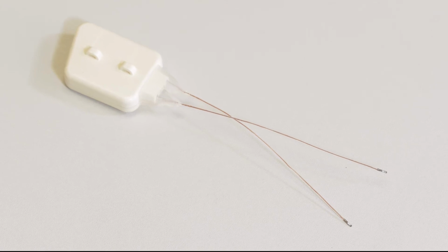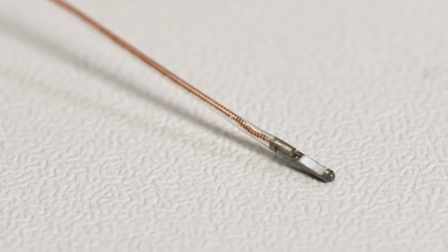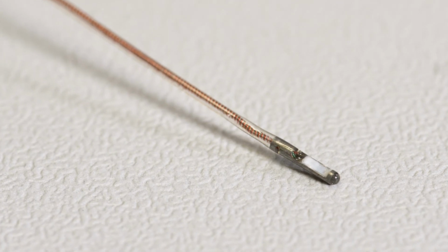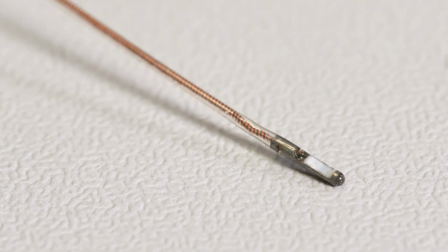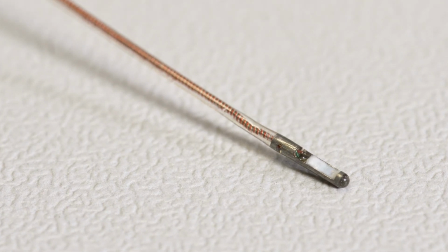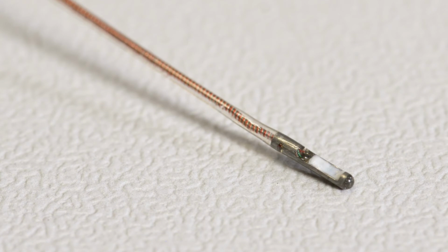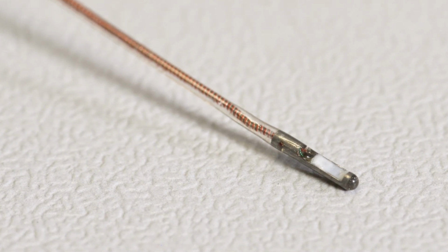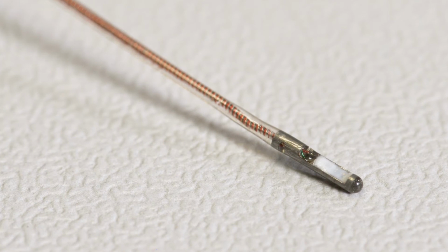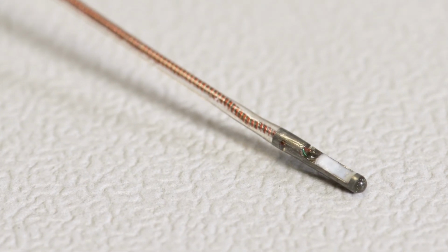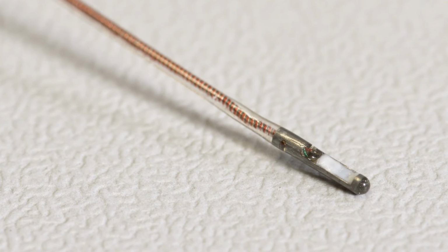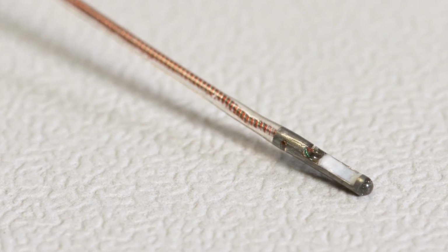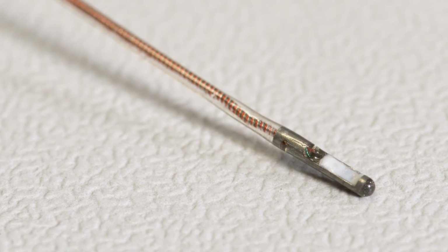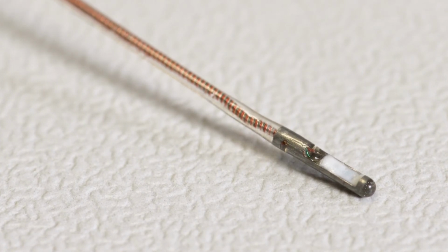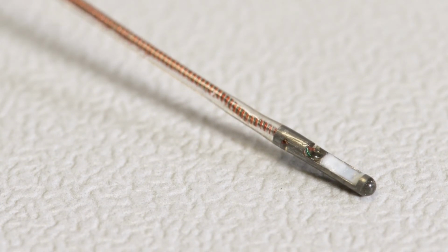All the Kaha Sciences pressure telemeters include a solid-state high-fidelity pressure sensor. This Millar Mikro-Tip pressure sensor is specifically designed to be fully implantable within the rat for chronic experiments. The solid-state pressure sensor is ideal for recording something like intracranial pressure, because it's such a low pressure signal that any effect of gravity on a fluid-filled catheter will change your reading of your intracranial pressure, whereas you don't get that with the solid-state pressure sensor. It's also ideal for recording signals such as left ventricular pressure, because it has a high fidelity signal and a high frequency response, so peak dP/dT values can be picked up accurately.